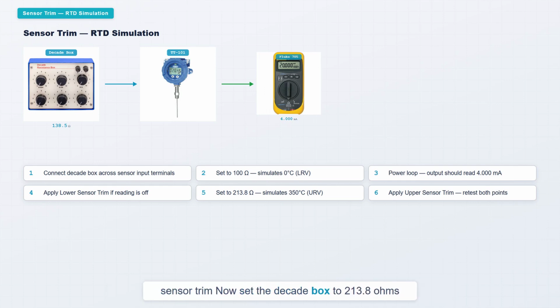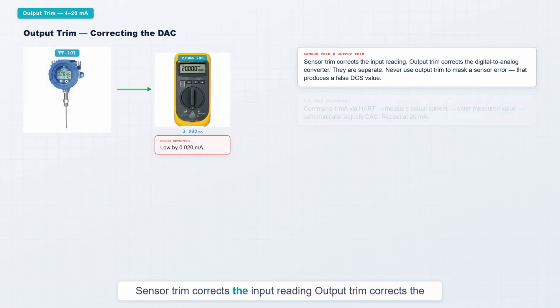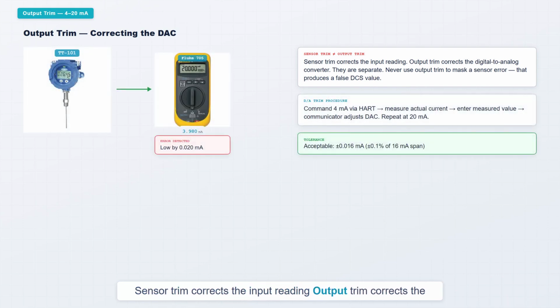Now set the decade box to 213.8 ohms to simulate 350 degrees Celsius. The output should reach 20.000 milliamps. Apply the upper sensor trim if needed. Run both points again to confirm you are within tolerance before disconnecting. Sensor trim corrects the input reading. Output trim corrects the analog output circuit. They are separate procedures and must not be confused.